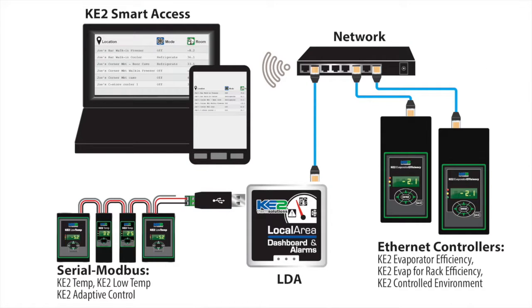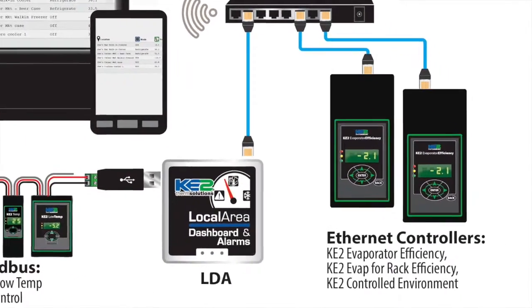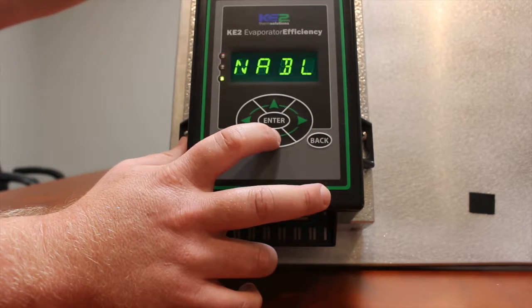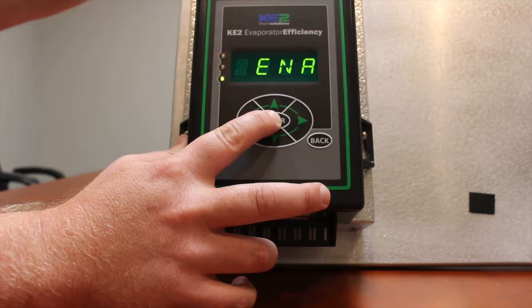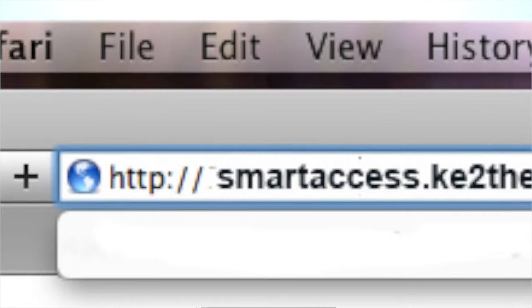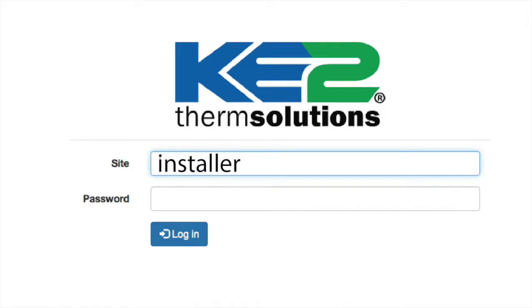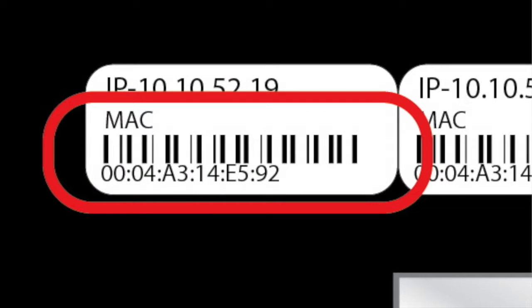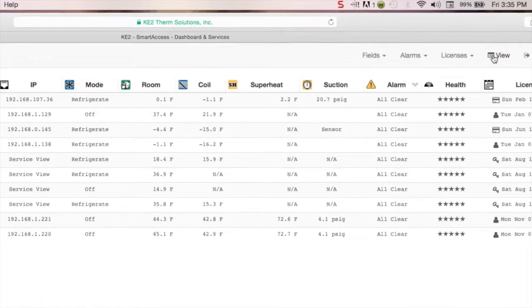With KE2 Smart Access, all the KE2 Evap or KE2 LDA needs is a physical connection to the network router with a CAT5 cable. With the KE2 Evap controllers, KE2 Smart Access is enabled in as little as three steps. When first setting up the controller, enable KE2 Smart Access in the Introduction Mode menu. Then go to smartaccess.ke2therm.net, enter the default information — the site should be Installer, and the password is the controller's MAC address, which is found on the back of the controller. And that's it — you're in business.